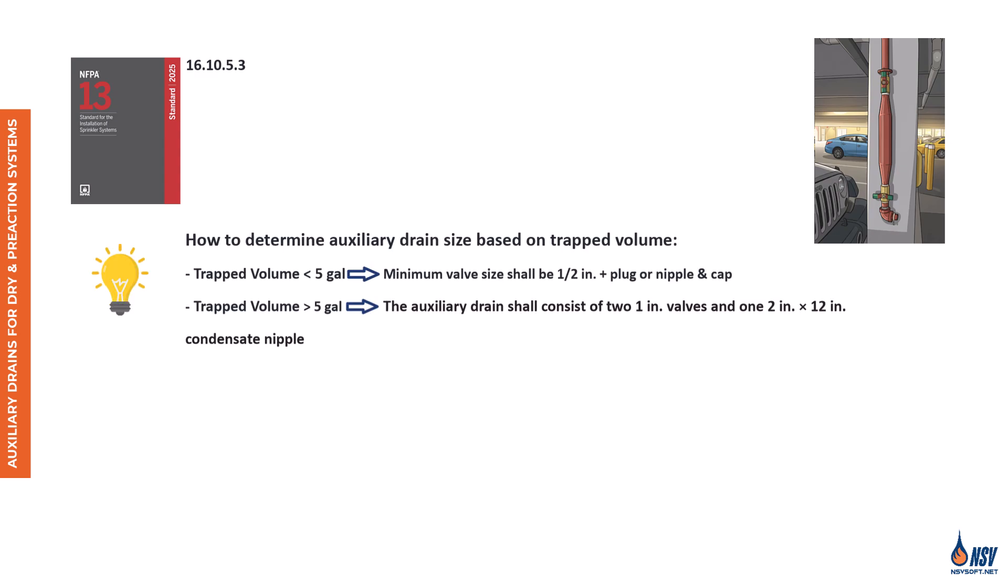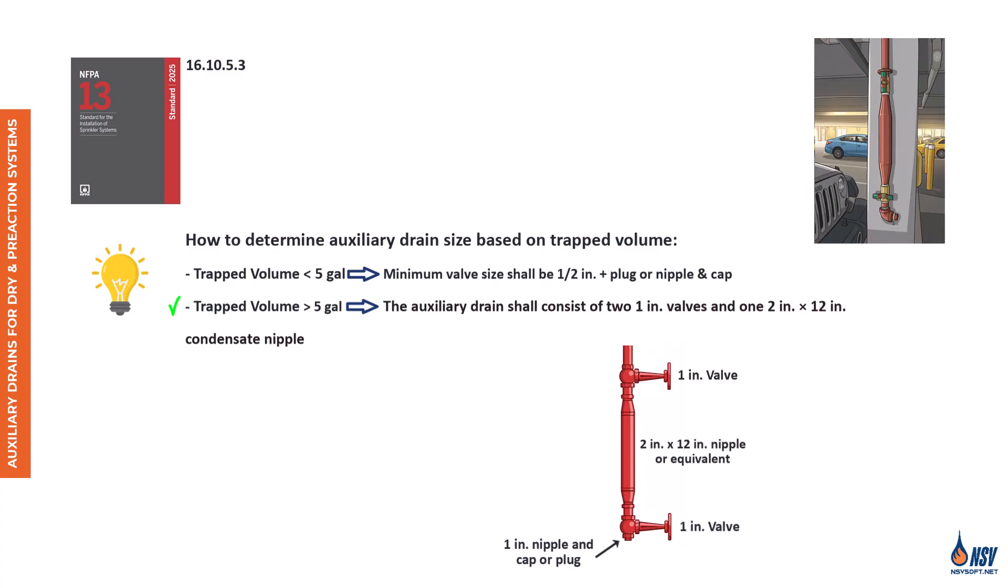To determine the proper size of an auxiliary drain, we need to consider the volume of trapped water in the system. If the trapped volume is less than 5 gallons, the drain must include a valve, not smaller than one half inch, along with a plug or a nipple and cap. If the trapped volume is greater than 5 gallons, the auxiliary drain must consist of two 1 inch valves and one 2 inch by 12 inch condensate nipple, or an equivalent listed device. This assembly, known as a drum drip, is installed at the low points of dry and pre-action systems. The drum drip functions like an air lock, allowing water to be drained without losing air pressure in the system. It provides a controlled way to remove condensate or trapped water, helping prevent corrosion and freeze damage, while maintaining system integrity.